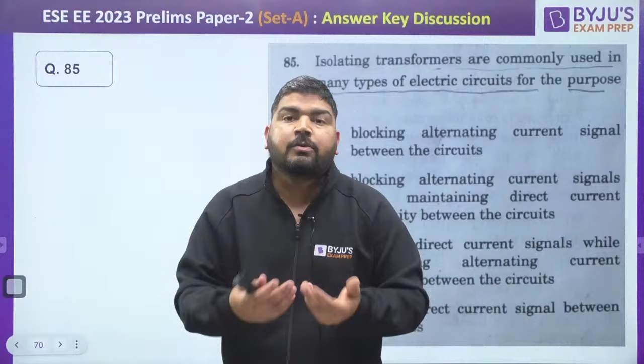Question 85: isolating transformers are commonly used in many types of electric circuits for the purpose of - isolating transformers are 1:1 transformers, turn ratio is generally 1. In an isolating transformer, DC cannot be passed to the secondary side, because with a DC component of current the flux becomes constant and the rate of change of flux becomes zero. That's why isolation transformers are used to block DC. So the answer is: blocking direct current signal while maintaining alternating current continuity between the circuits - that is option C.